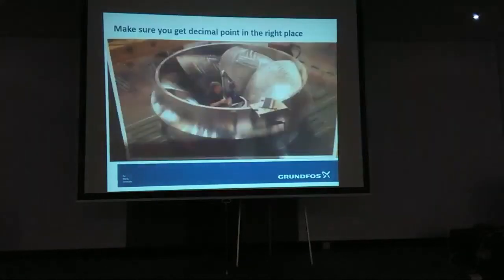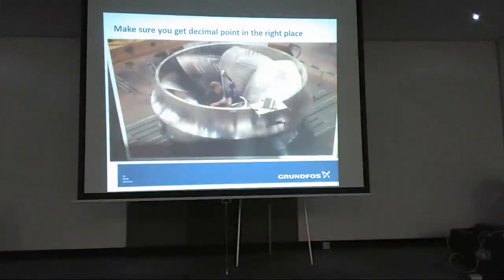decimal point in the wrong place, that can happen. If that lands on site, it ain't coming back. This isn't one of those, by the way, I just found it on the internet. So that is a real impeller on something in a power station somewhere. We do sometimes get people doing calculations in litres a second, going onto a website and working in cubic metres per hour, so the pump's undersized, or they've worked in 2,000 litres a minute, sized the pump in litres a second, and it's gone. But they do sometimes come out. So just be mindful, pumps of that size do exist.